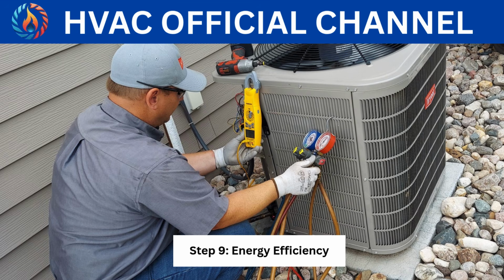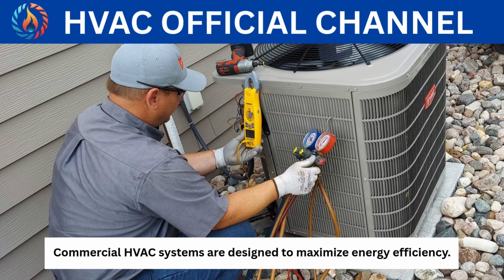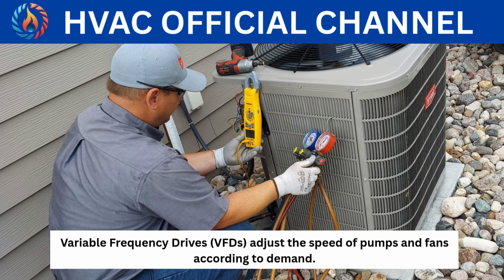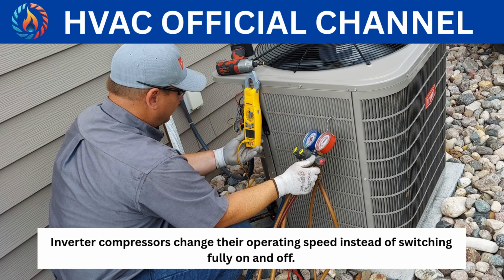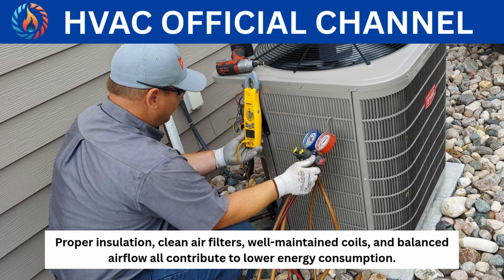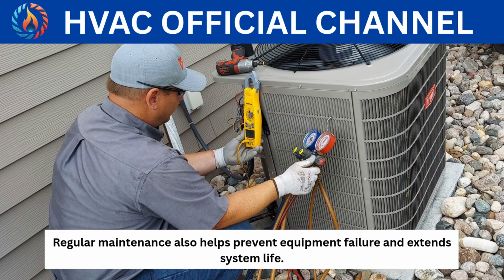Step 9. Energy efficiency. Commercial HVAC systems are designed to maximize energy efficiency. Variable frequency drives adjust the speed of pumps and fans according to demand. Inverter compressors change their operating speed instead of switching fully on and off. Proper insulation, clean air filters, well-maintained coils, and balanced airflow all contribute to lower energy consumption. Regular maintenance also helps prevent equipment failure and extends system life.